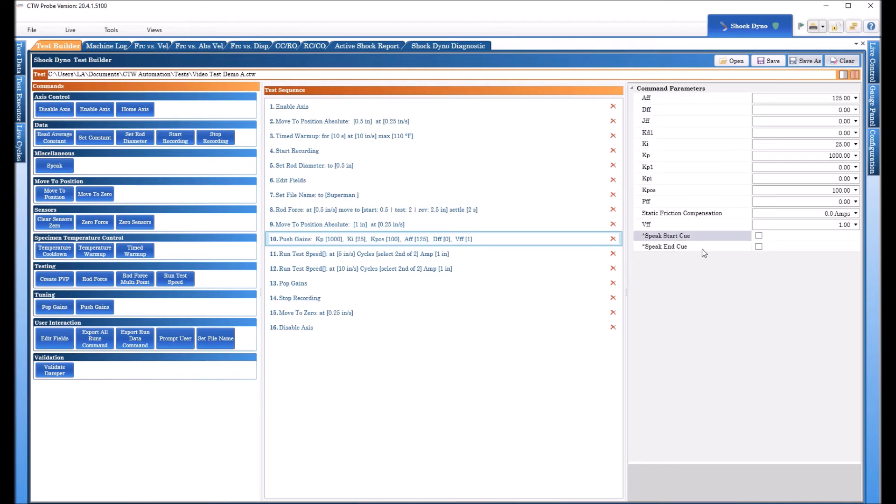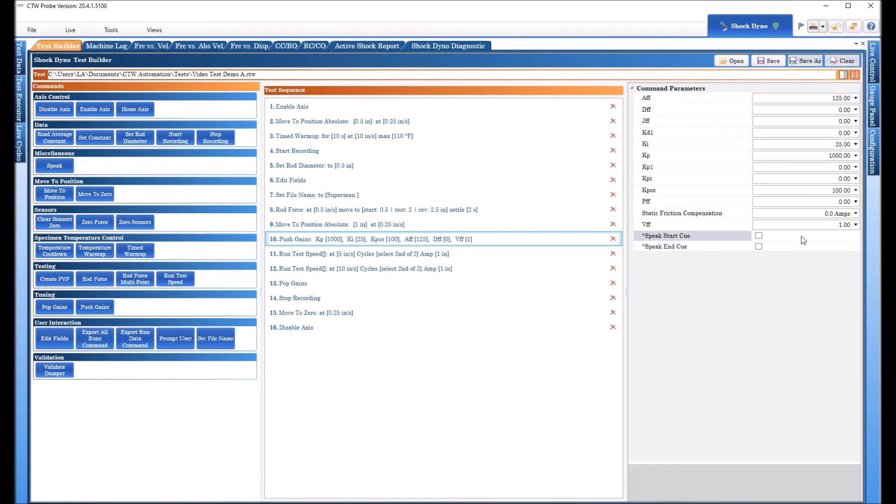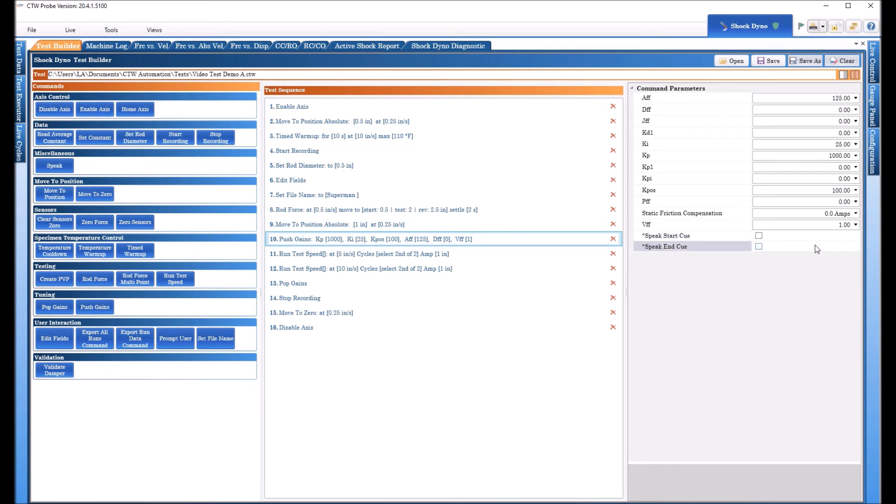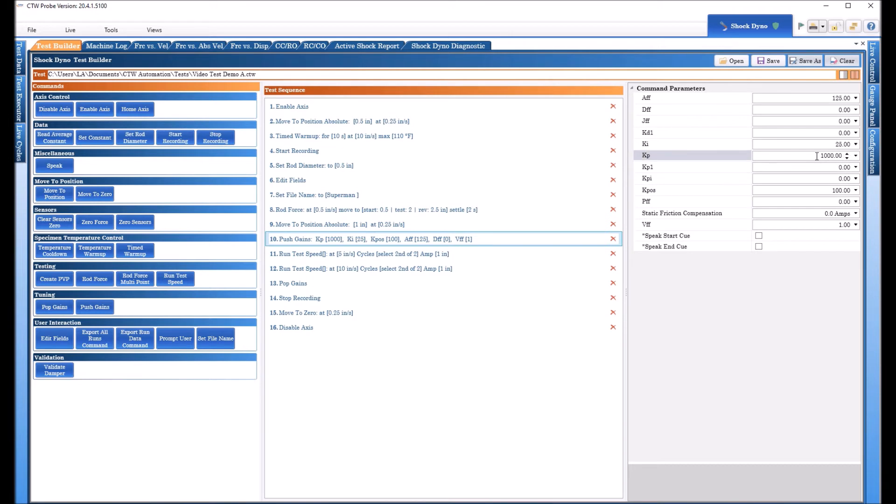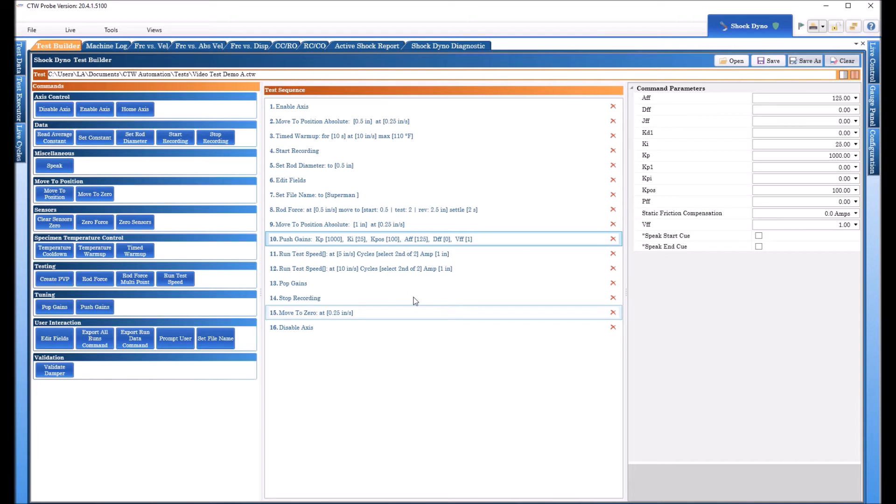So now we've gotten that ready we go to our push gains our performance gains we talked about that a little bit in the last video. This is basically how hard we tell the linear actuator to move and how hard it follows the command. Now these are all PID loops these all tell the actuator to do position velocity acceleration and how hard to maintain all of those things. If you get too extreme then you will start to have your actuator squeal and I don't think anybody in the office adjoining will be happy. So we want to use these numbers within a reason work with us and we will help you get whatever you want to do for performance.